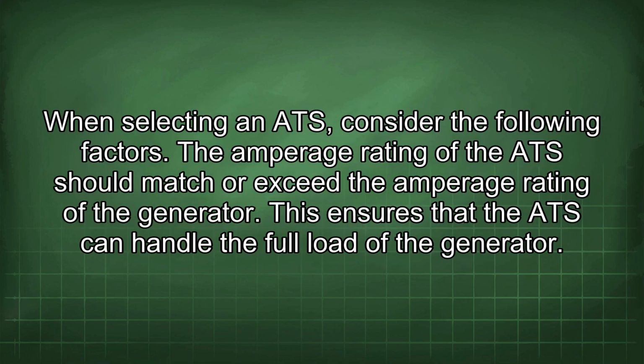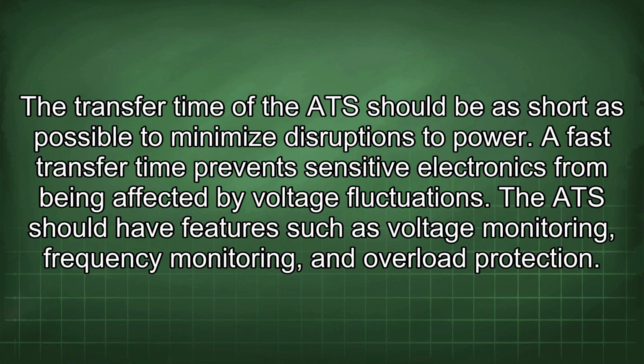When selecting an ATS, consider the following factors. The amperage rating of the ATS should match or exceed the amperage rating of the generator. This ensures that the ATS can handle the full load of the generator. The transfer time of the ATS should be as short as possible to minimize disruptions to power. A fast transfer time prevents sensitive electronics from being affected by voltage fluctuations.